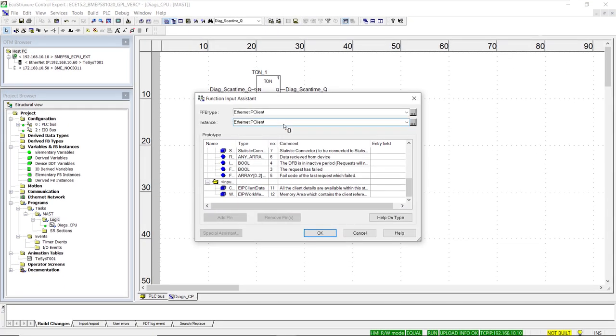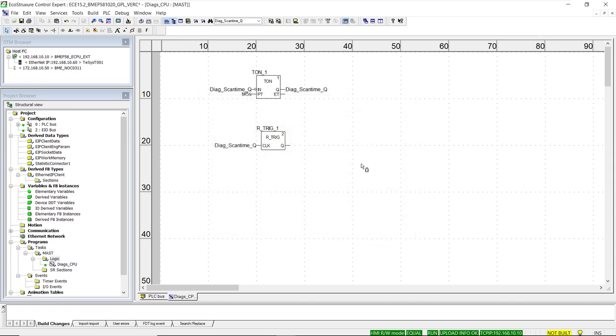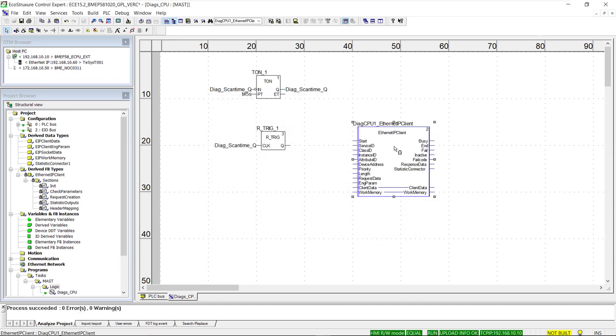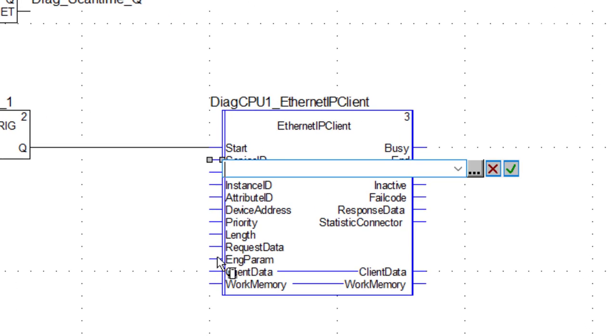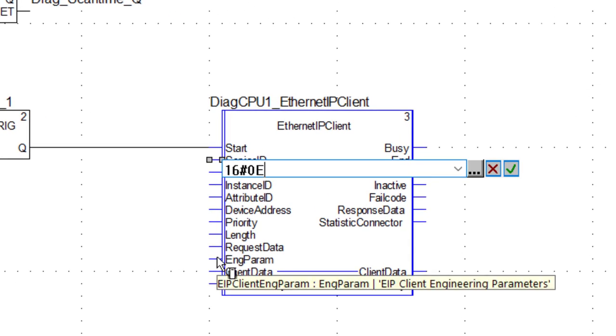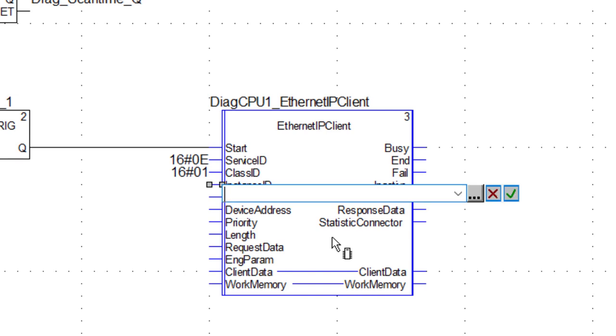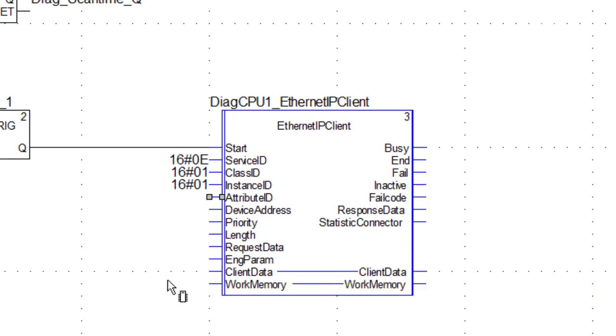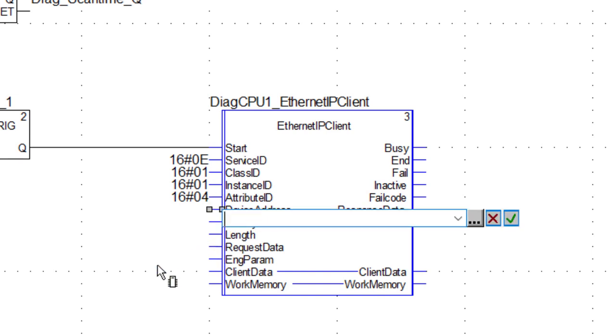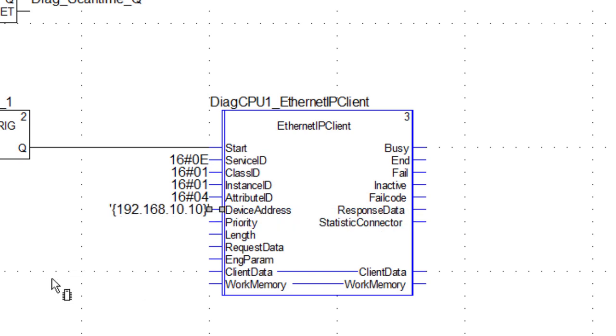Following best practices, the instance name has a prefix we define, followed by an underscore and the name of the function block itself. We interconnect the rising edge detection function block with our Ethernet IP client function block, then populate the values and structures for each pin. We start by entering the service code and the class, instance, and attribute parameters, which can be in hexadecimal or decimal format. Then we add the device address, which is the IP address of the target in curly brackets.